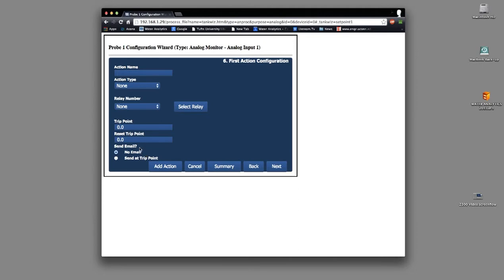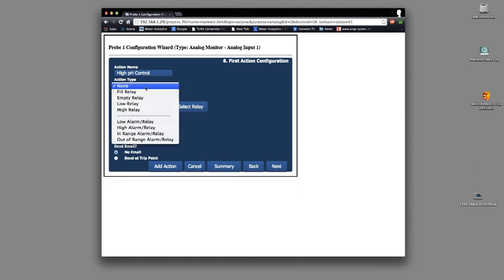Let's suppose we have a process in a tank that must be kept below a pH of 8.5. At higher levels, a pump dispenses acid into the tank. Okay, let's set up a relay for that. First, I'll give the relay a name. I'm going to choose high pH control. On the pull-down menu for action type 1, I'm going to choose high relay.